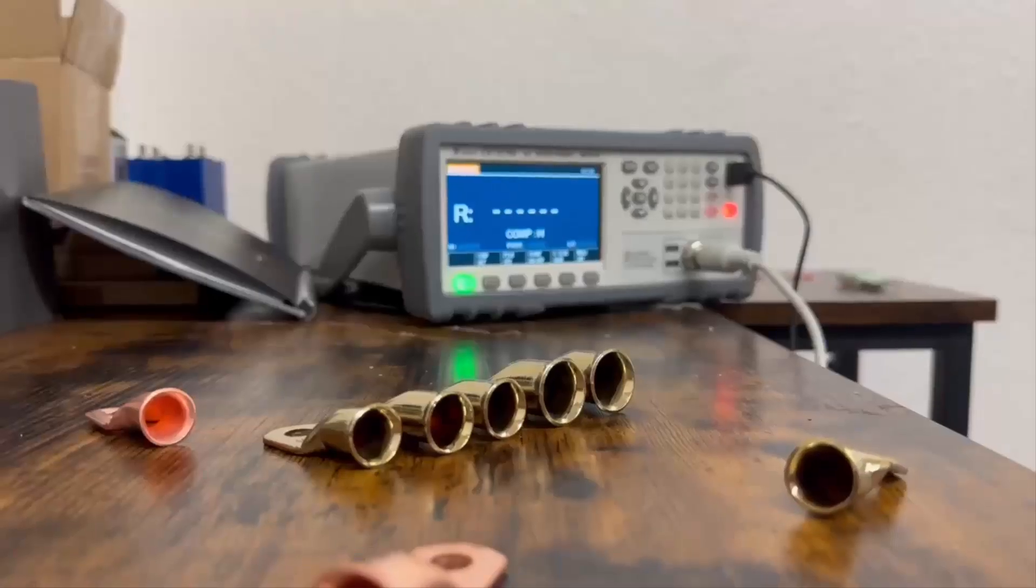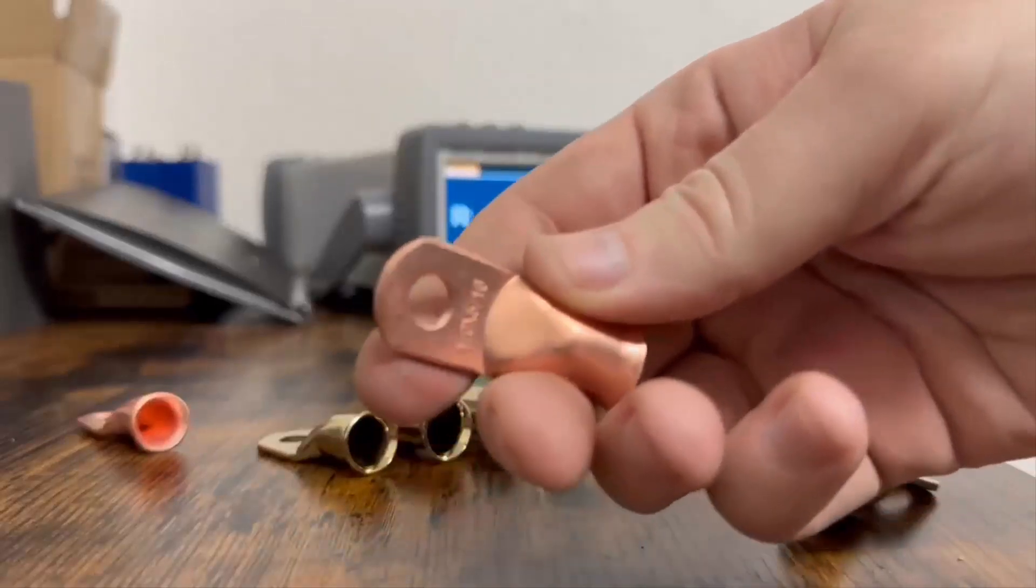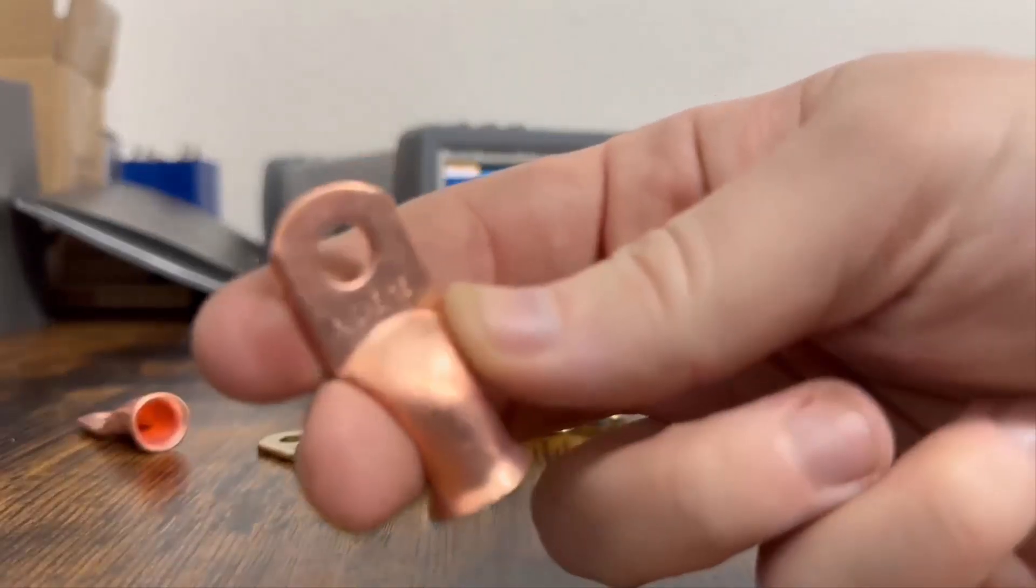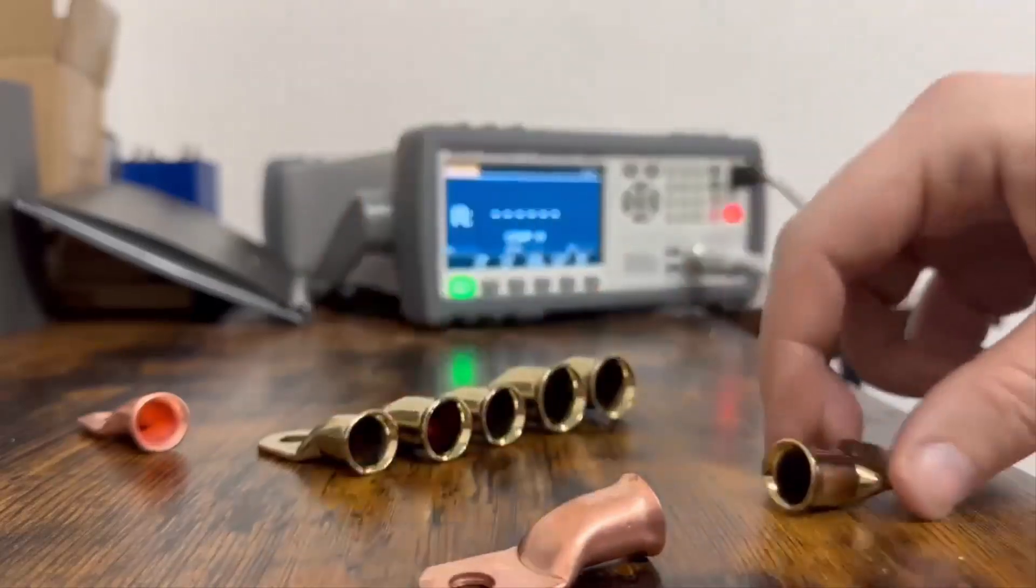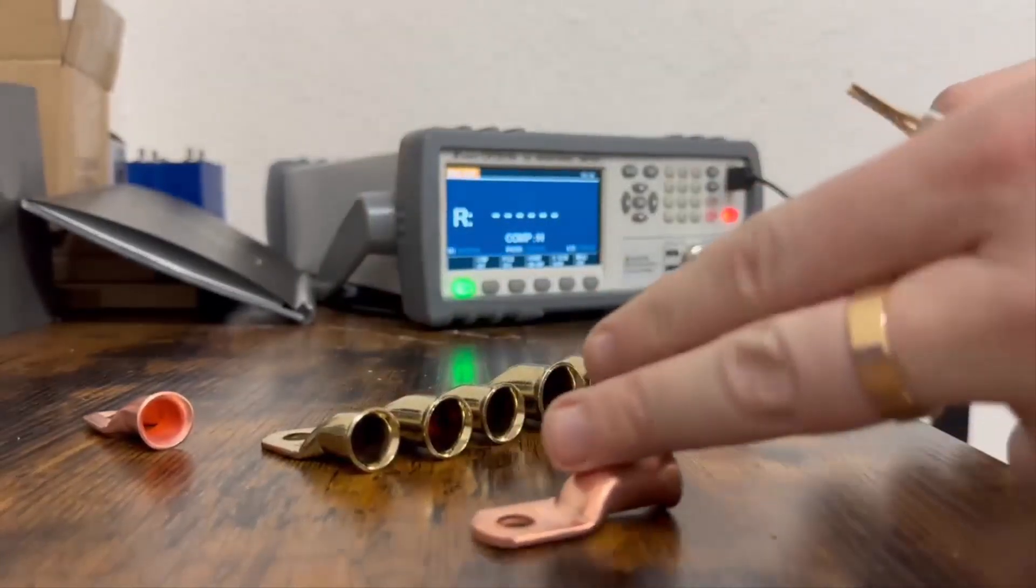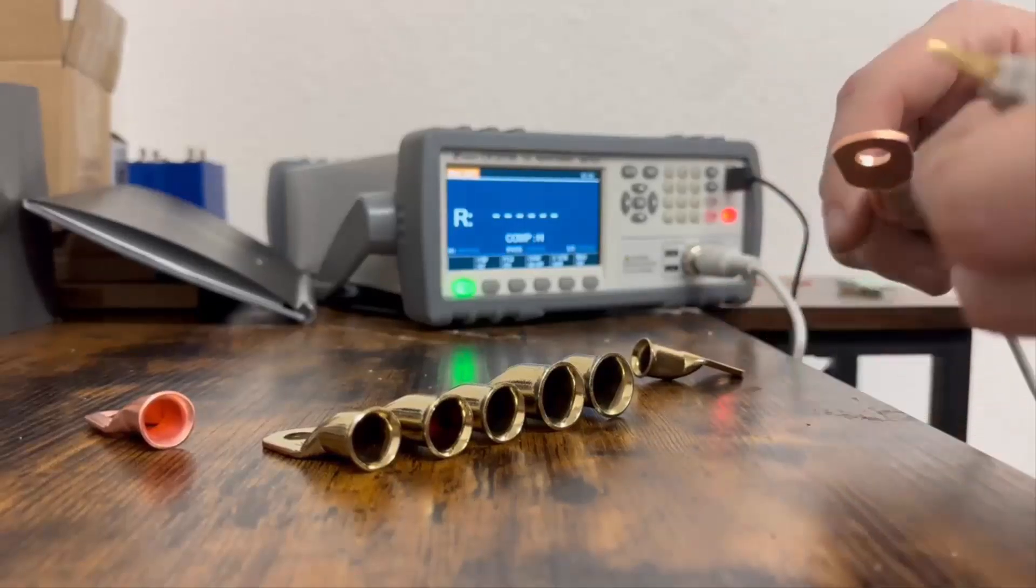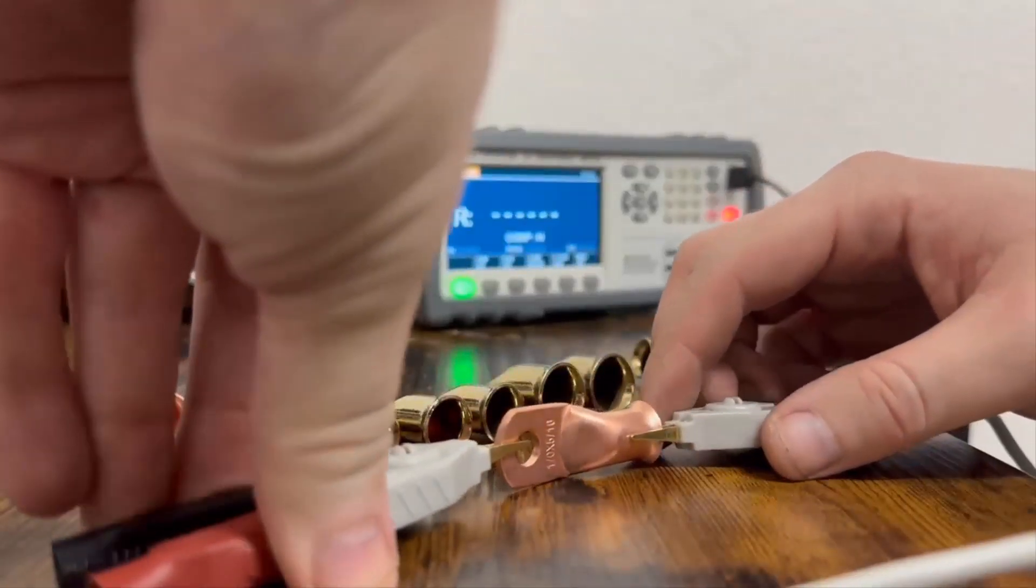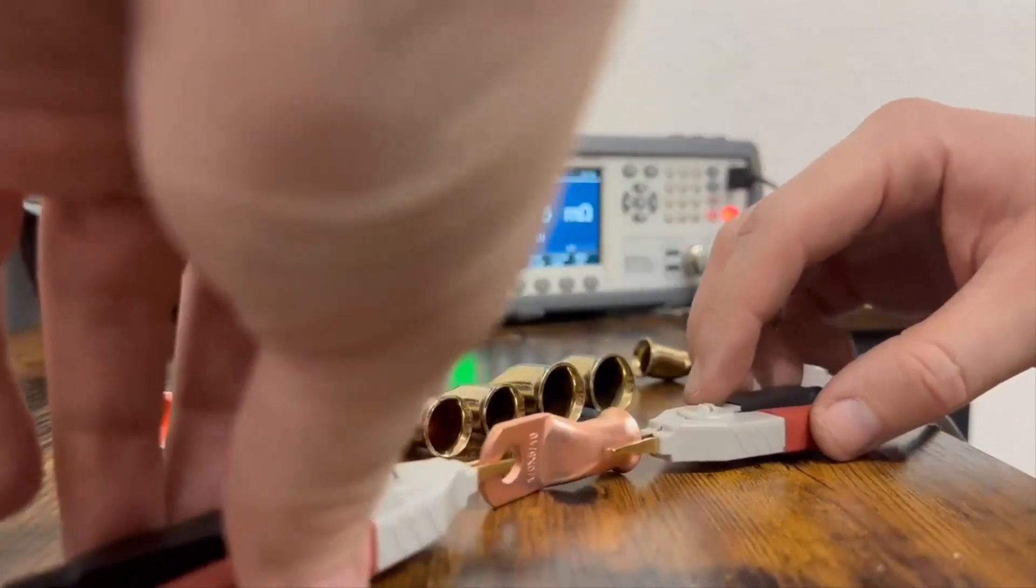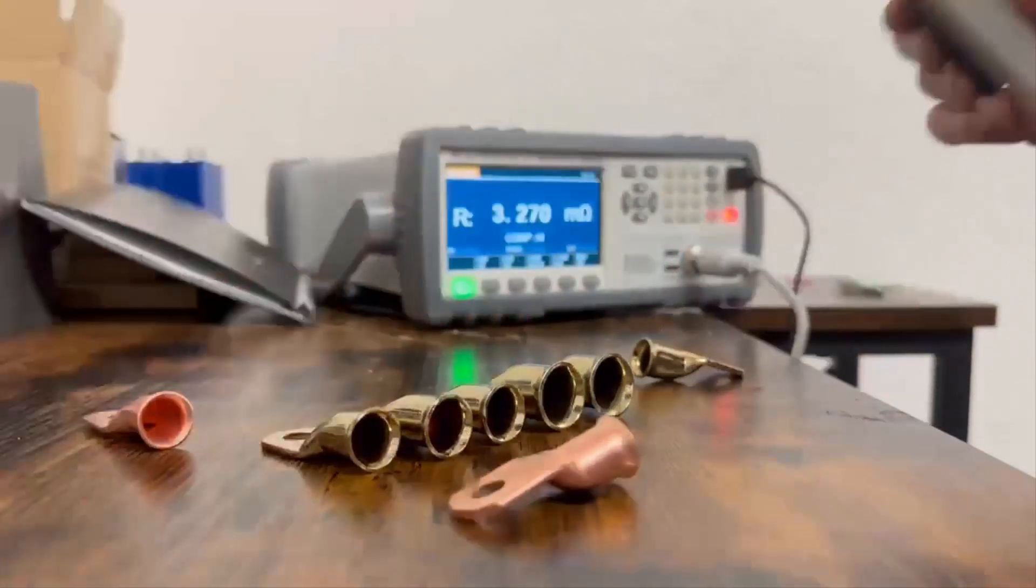First we're going to test the resistance of a standard one-zero American wire gauge lug. This is a 5/16 inch inner diameter lug and is pure copper. When we measure the direct current resistance of this lug, we get a result of approximately 3.27 milliohms.